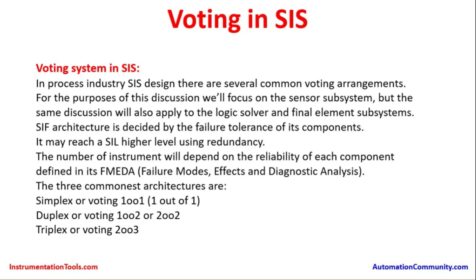FMEDA stands for Failure Modes, Effects and Diagnostic Analysis. These are terminologies we will understand in more detail in dedicated training on the safety instrumented system. The three common architectures are: simplex or 1 out of 1 (1oo1), duplex or 1 out of 2 / 2 out of 2 (1oo2/2oo2), and triplex or 2 out of 3 (2oo3).